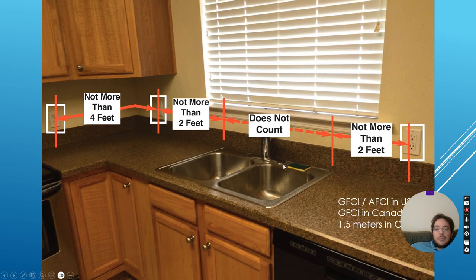Now, in Canada, the receptacles have to be much closer, so they have to be within 900 millimeters of each other, or 3 feet. And any receptacle within 1.5 meters of the sink has to have the GFCI rating, but anything past that does not. So there was an argument over whether the stove needed to have a GFCI rating, and in Canada the answer is no, but in the US the answer is yes if it's within 6 feet. But now it doesn't matter. The stove has to be GFCI even though it's a massive load.